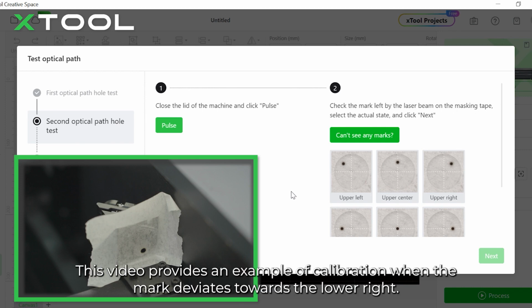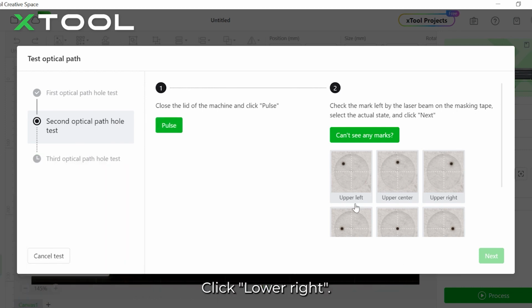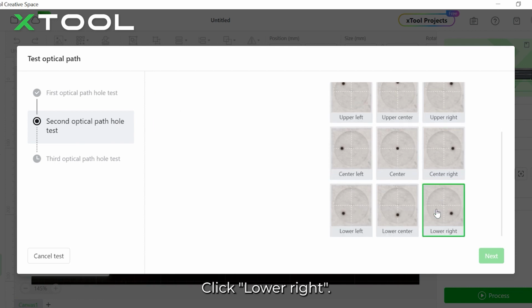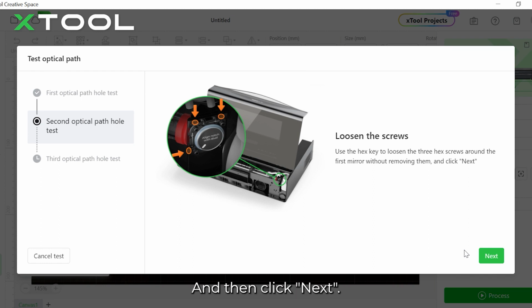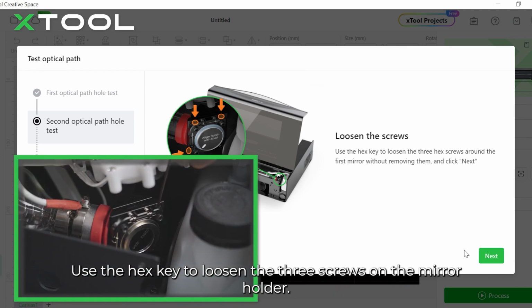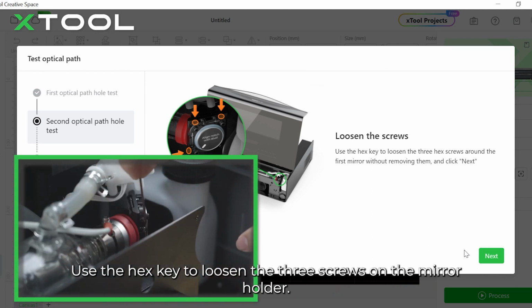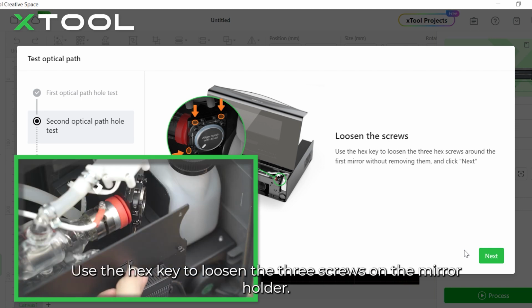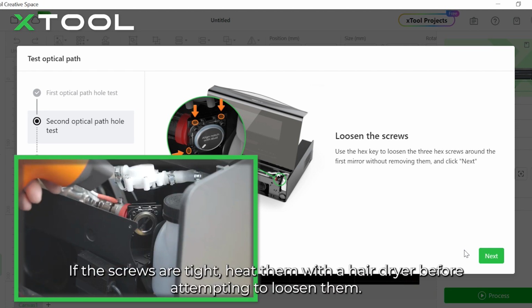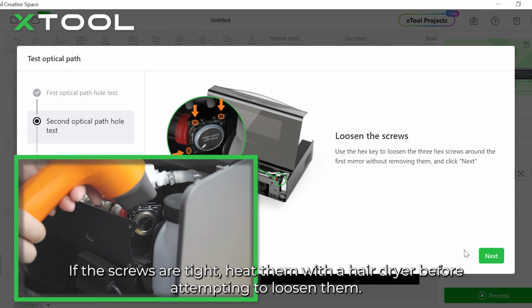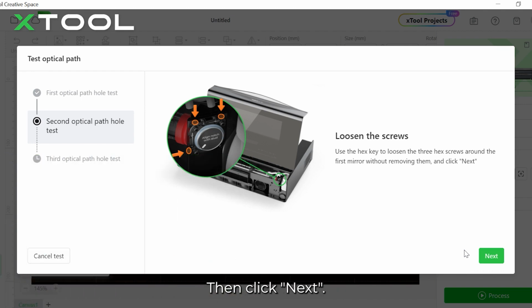This video provides an example of calibration when the mark deviates towards the lower right. Click Lower Right. And then click Next. Use the hex key to loosen the 3 screws on the mirror holder. If the screws are tight, heat them with a hair dryer before attempting to loosen them. Then click Next.